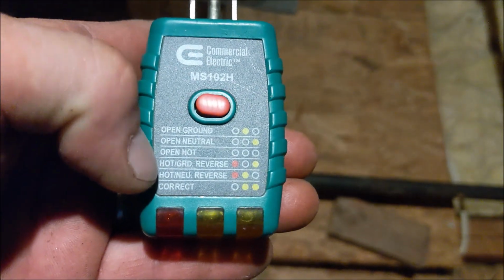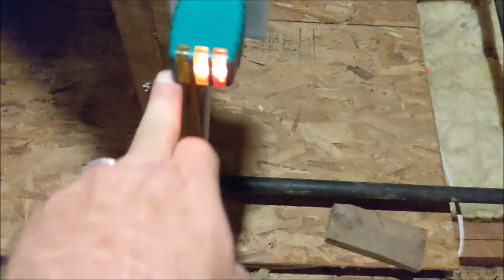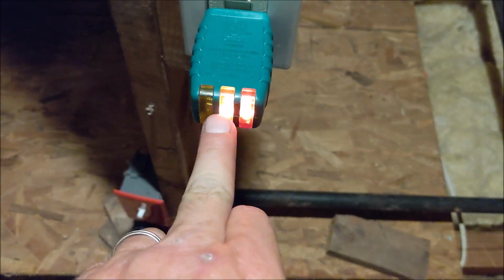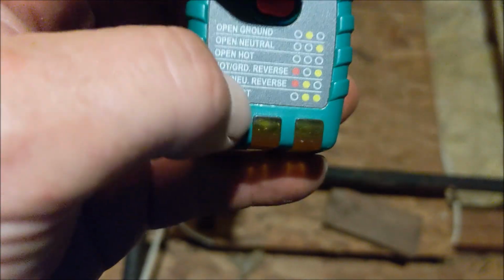So we have a hot and neutral reversed where the red and yellow and the wires are backwards. This is at the attic GFCI outlet. As you can see, we should have two yellows or two oranges. We have an orange and a red. So the orange and a red is this one right here, hot and neutral reversed.